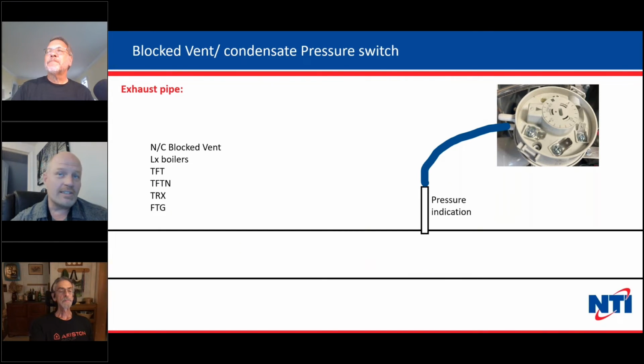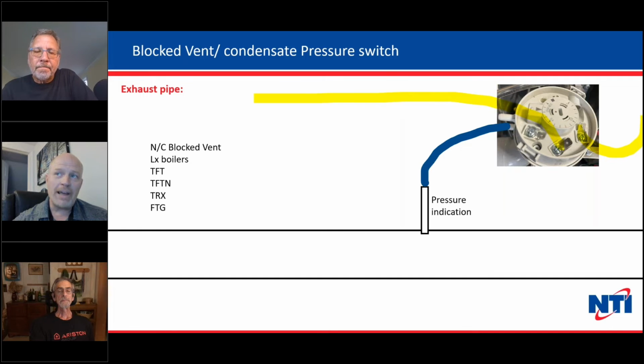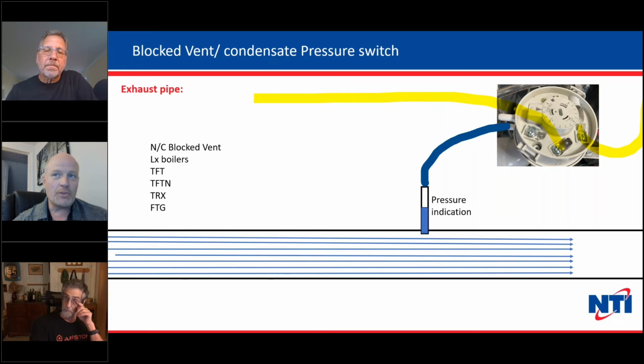We also use these switches, the same exact switch, but a different application. And we use it as a normally closed blocked vent switch. So these are used on LX boilers. Also on the LX, it's the big silver switch. On the TFT, TFTN, the TRX Series 2 and FTG products, we use this as a condensate blocked exhaust switch. And the way it works is fairly simple. Again, we allow power to pass through a set of normally closed contacts this time. And as long as everybody's happy and we've got good flow, we see a small pressure change on the one tube and the switch allows power to pass.